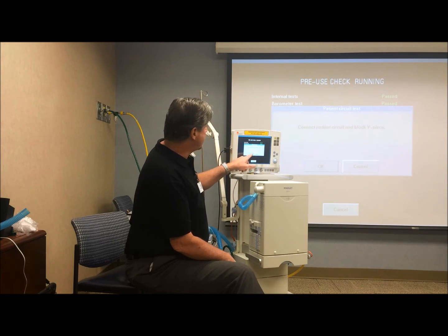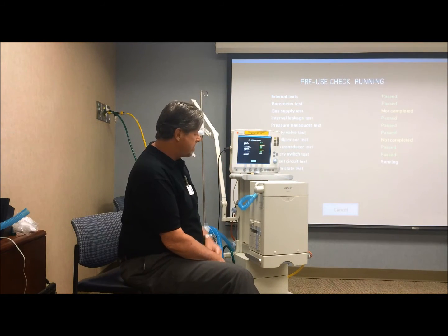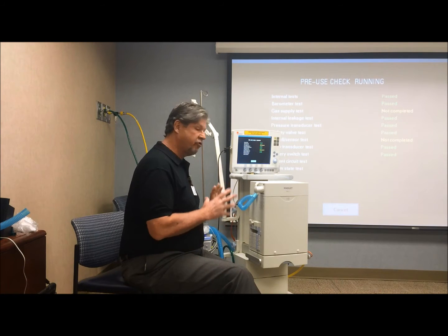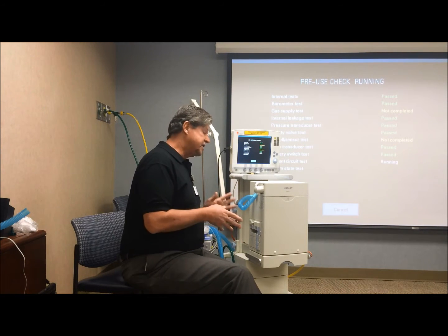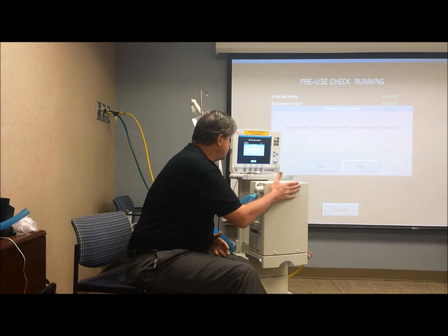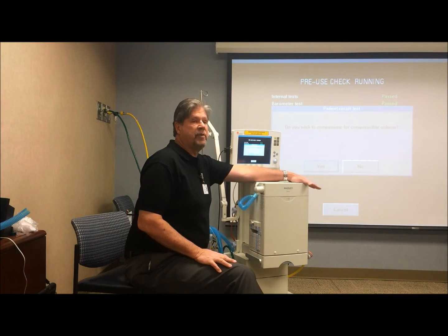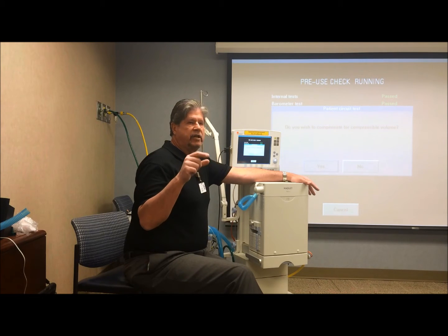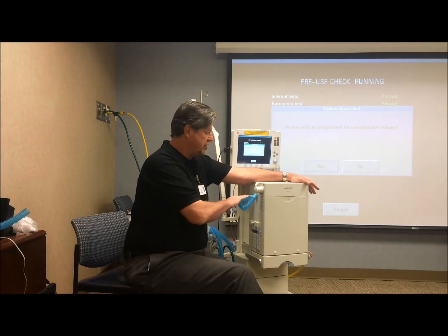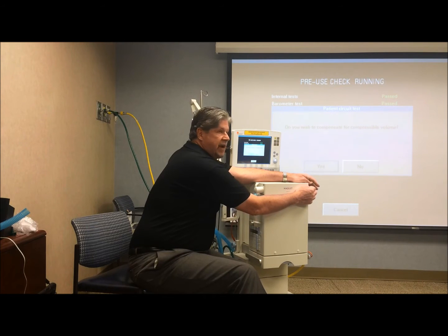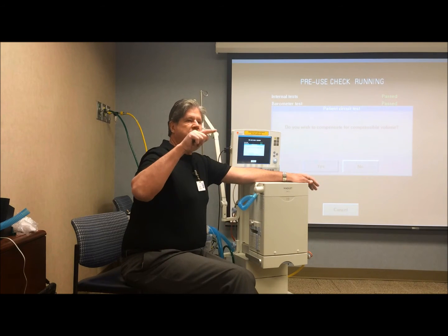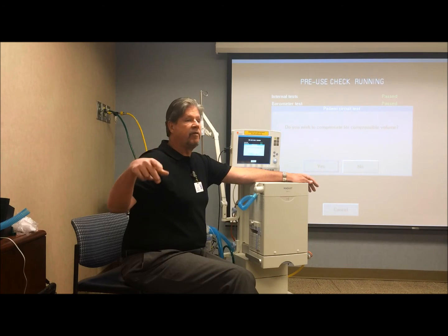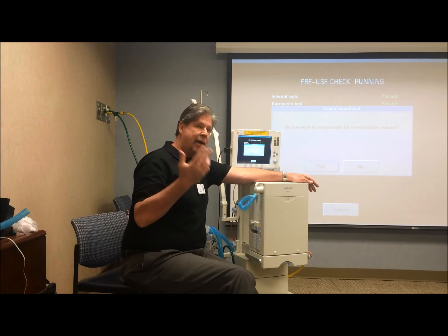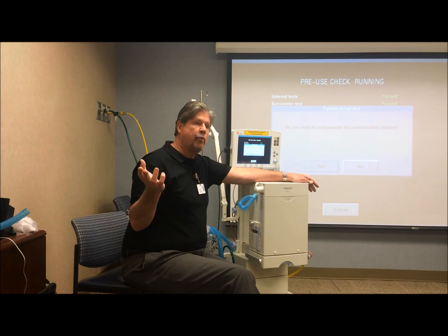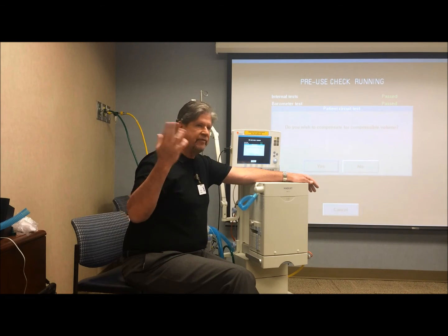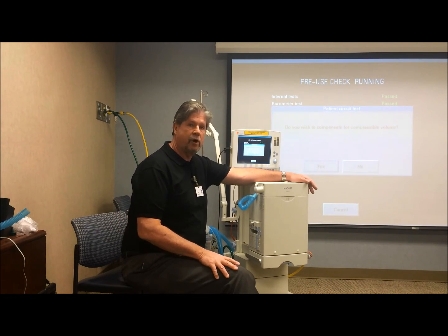So we connect the patient circuit and block the Y piece. We say okay, and now it's pressurizing that circuit. It's looking for a drop in pressure. If it doesn't see a drop in pressure, there are no leaks, and when it releases the pressure, it measures the volume that comes out. So if it knows that it delivered 20 centimeters of water pressure to the circuit and 20 cc's of volume comes out, then it loses 1 cc per centimeter of water pressure, because it's how many cc's divided by the amount of pressure that was created.